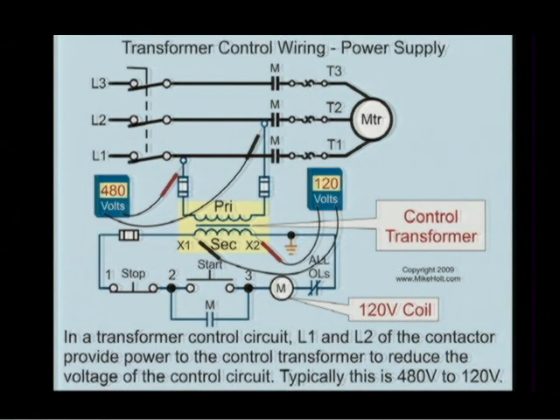We got a 480-volt system. Line 1, 2, 3 coming in, main contacts in the motor, T1, 2, 3 going to the motor. These are my overloads. I want to operate a 120-volt control circuit, so I put a transformer. Now, do I put a transformer, or do I just buy a starter that has a transformer and the primary is already pre-wired with the fuse protection? Is that the way it is?